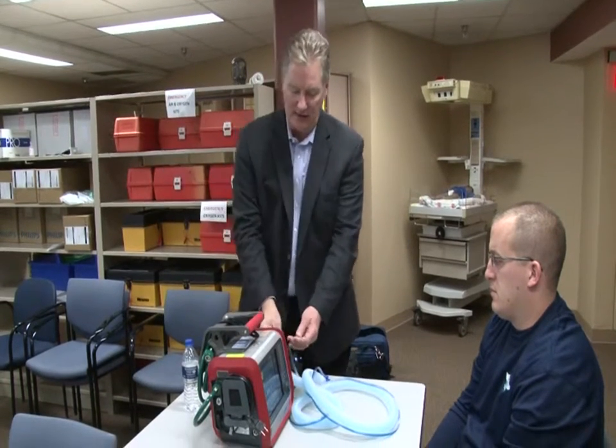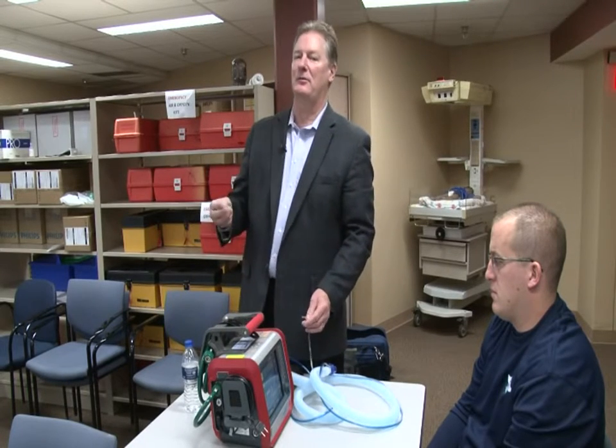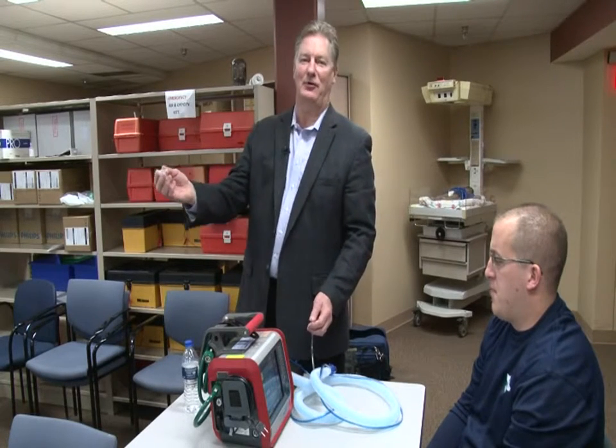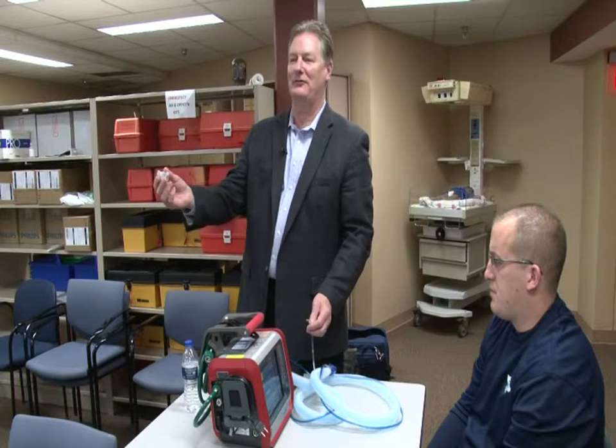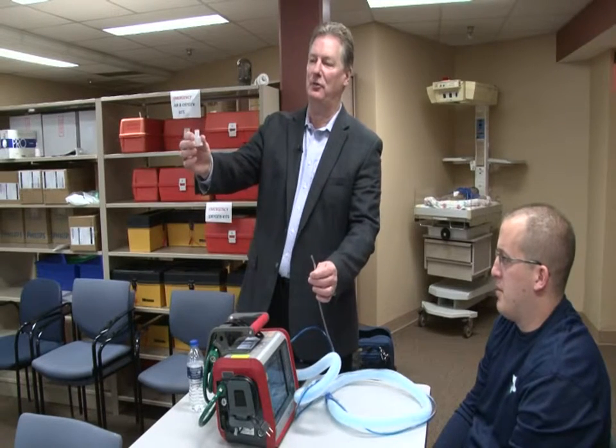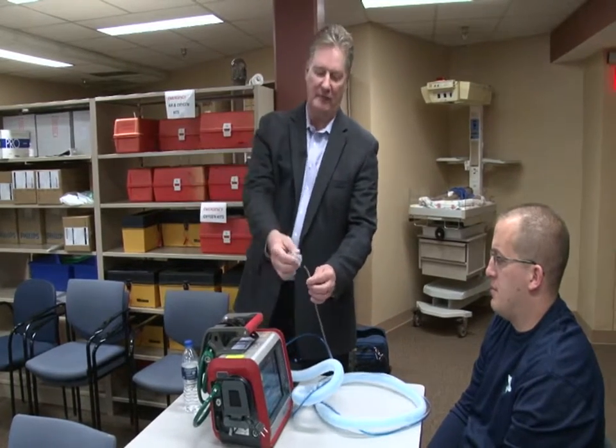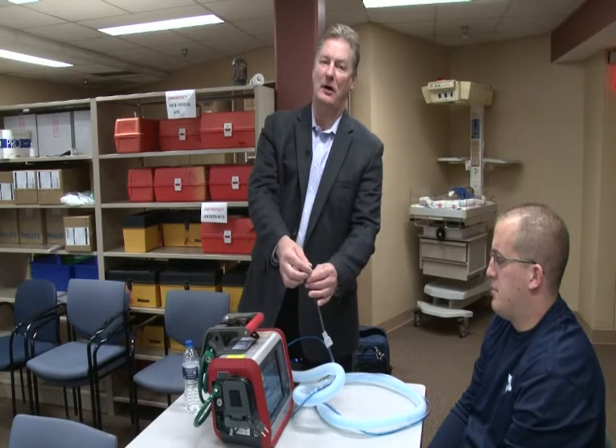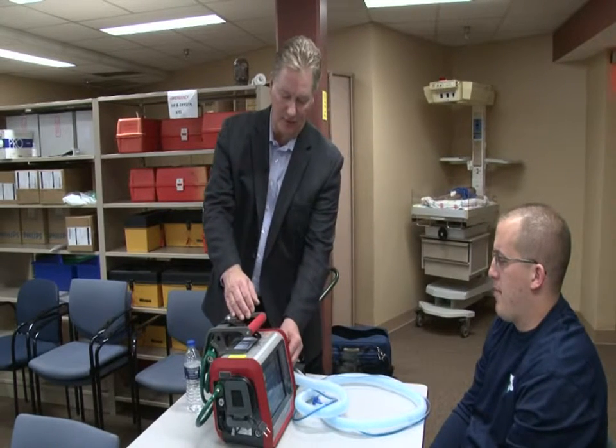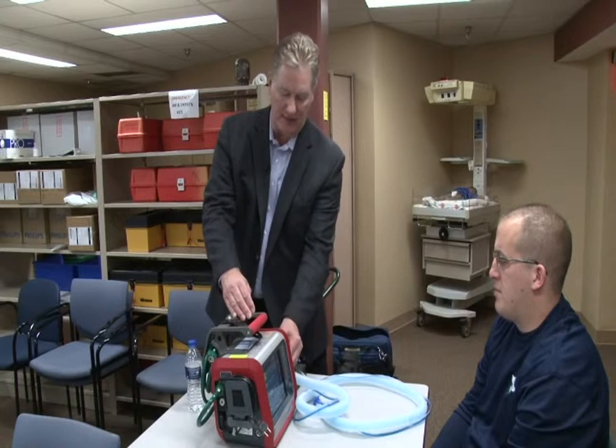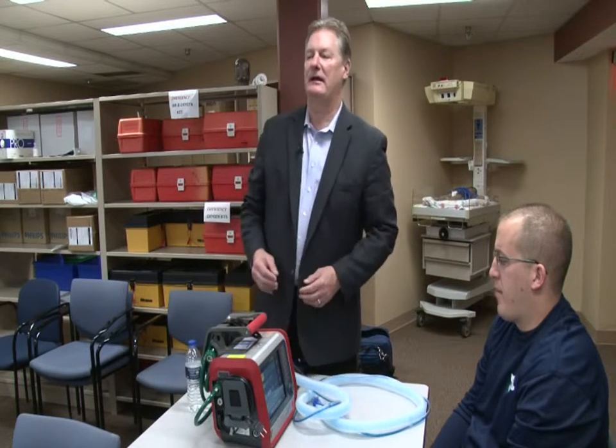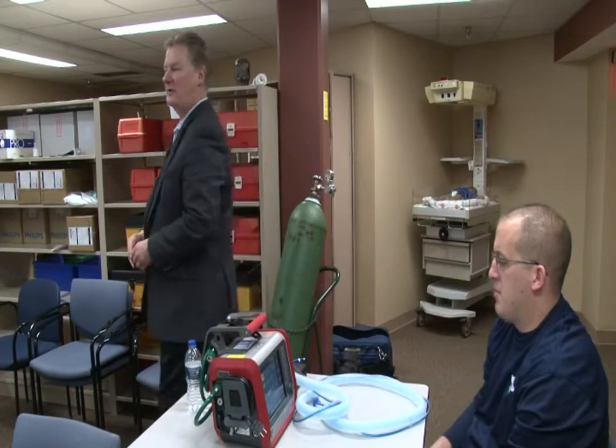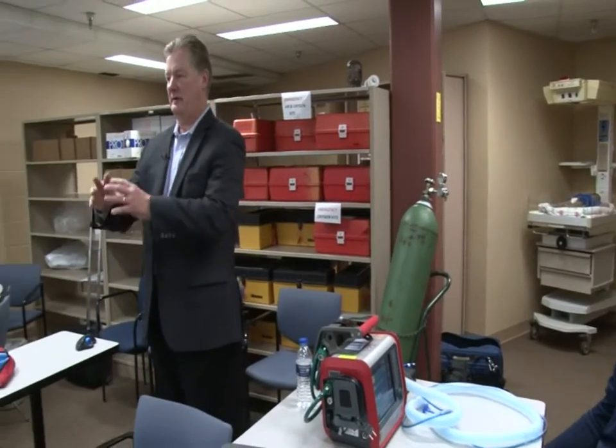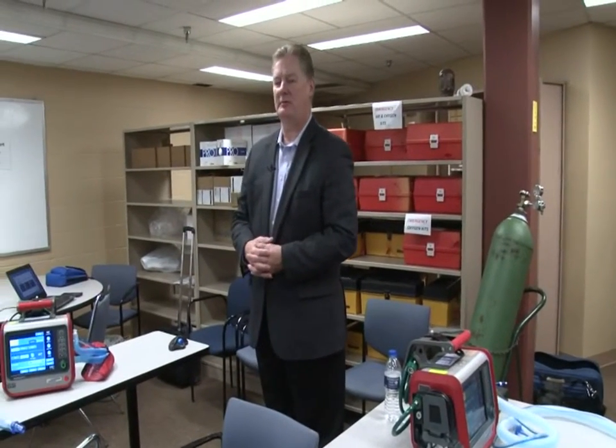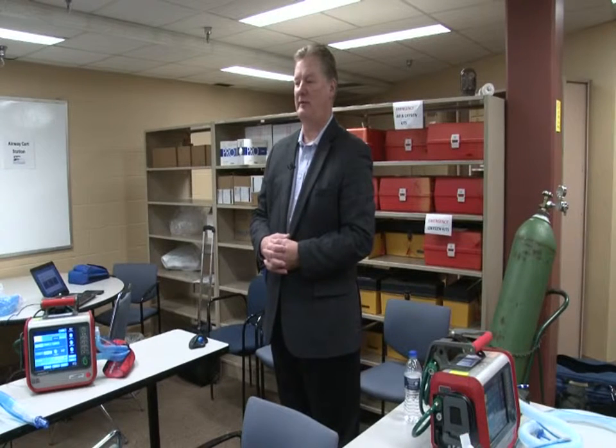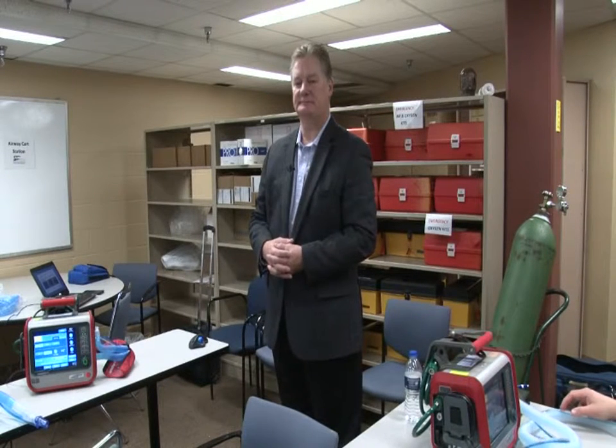If I said you'll never need it again till the next time you calibrate one, the next time you used it, you'd be prompted to calibrate the flow sensor. So what I suggest is just pull either the blue or the clear tube off, feed the adapter onto the hose, and then reconnect the hose. That way, in the rare instance you would need it again, you're going to know exactly where it is. And then after the run, when you're pulling the circuit off, just pull everything off together and throw it away. Okay?